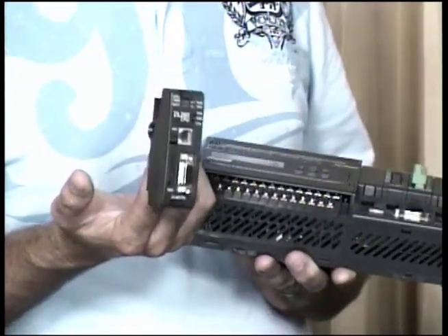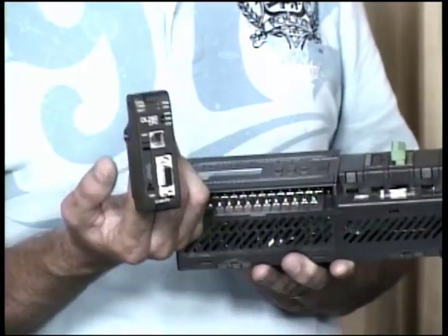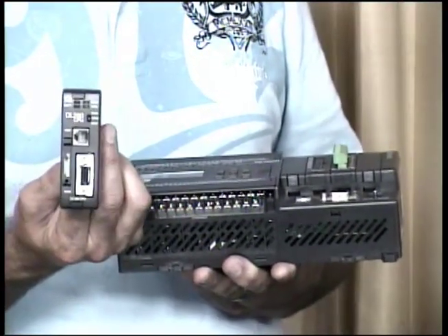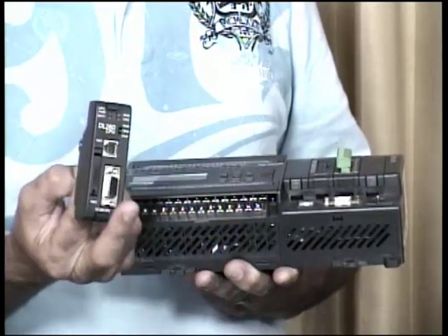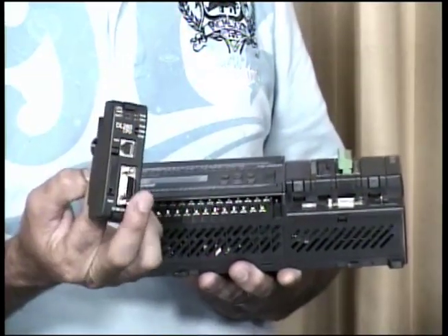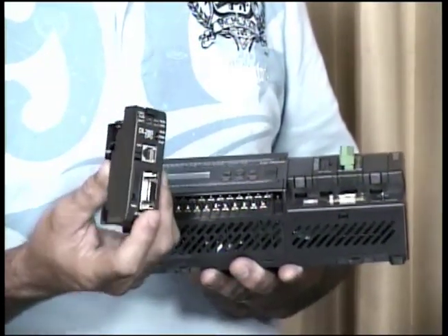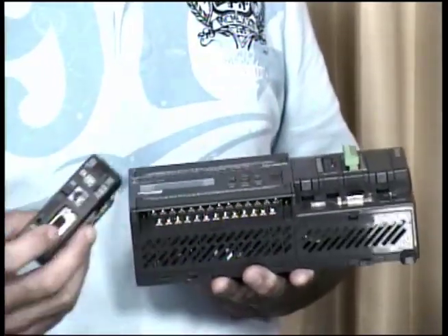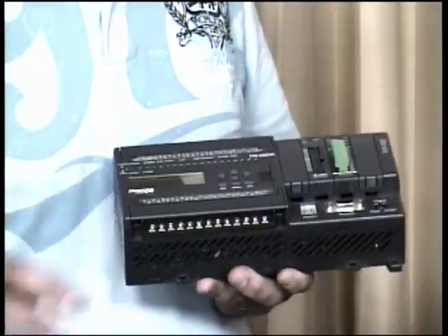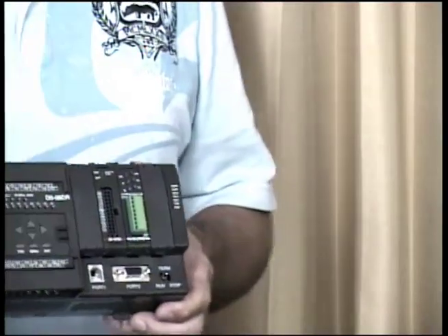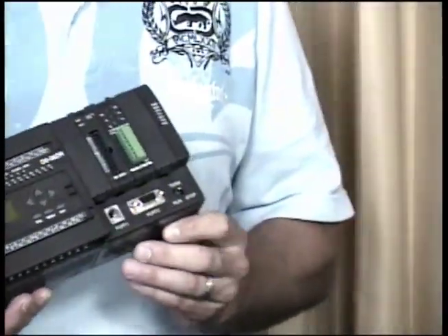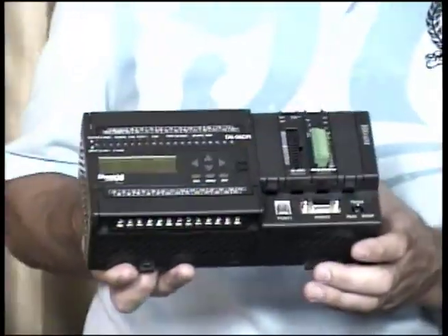Yeah, with the 260, you're going to be able to put hundreds of I/O because you can put it in a 205 rack. You can have expansion on the 205 rack, so you can have multiple racks. You can also have remote I/O. You can do remote I/O off the bottom, or you can network off this bottom port. So you can have a lot of I/O. But other than that, if you want to know the truth, it's pretty much the same processor. There's a couple little hidden things that we can't really tell you, but yeah, it's the same processor.